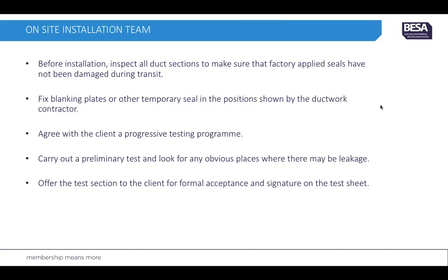The installation team also needs to agree with the client on a progressive testing programme. Ideally they should carry out a preliminary test to look for any obvious places where there may be leakage — there may possibly be an access door missing, or a duct joint completely broken, and obviously you would never get a satisfactory test result in that case. You then need to offer the test section to the client for formal acceptance and signature on the test certificate.